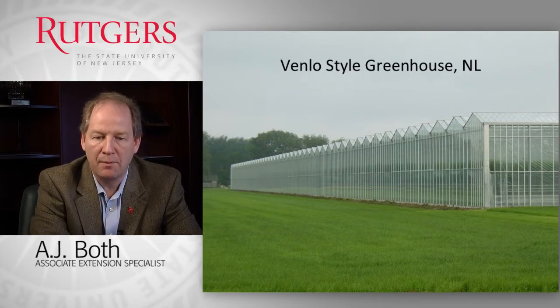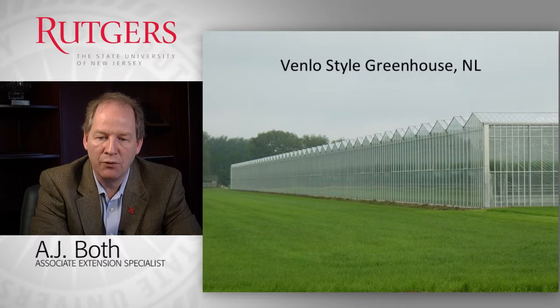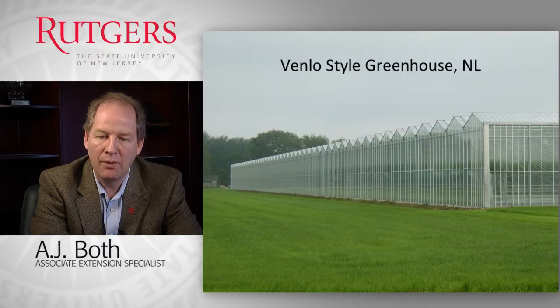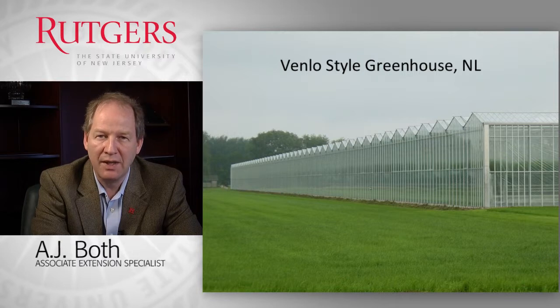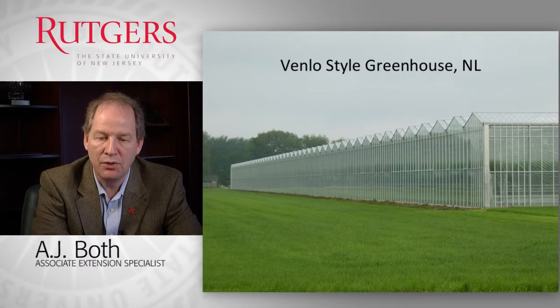We can also use Venlo-style greenhouses. These are typically also naturally ventilated with windows only in the roof and no side windows. They rely on their height — the stack effect or chimney effect generates air to rise to the peak to exit the greenhouse. More so they rely on the wind effect, where wind pressures generated by airflow around and over the greenhouse create pressure differences that help move air through the structure. If outside conditions are not too warm and you have sufficient wind, these systems are very useful for ventilating greenhouses without mechanical fans that require electricity.